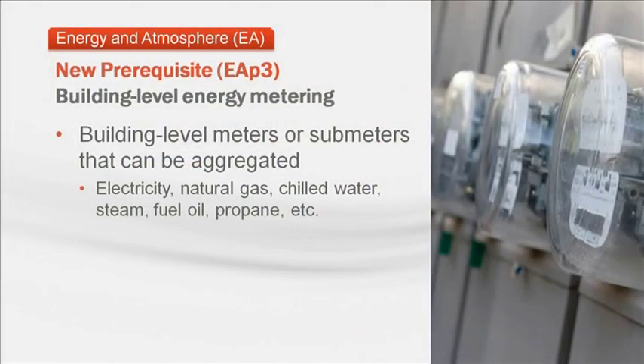Now, as mentioned earlier, there's a new prerequisite to meter building energy use by type. Either building or aggregated sub-metering is required for all the energy uses in the building. Depending on the energy sources, this may be a significant increase in metering. And remember, this is a prerequisite.